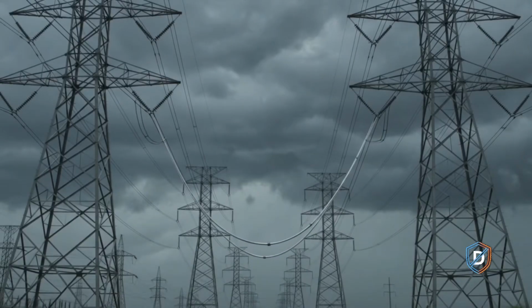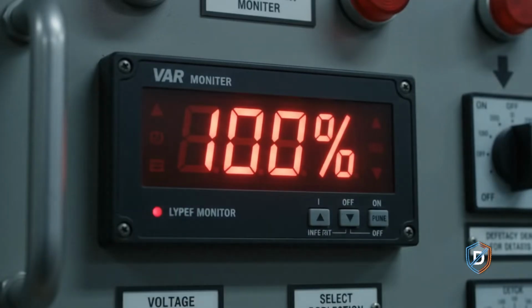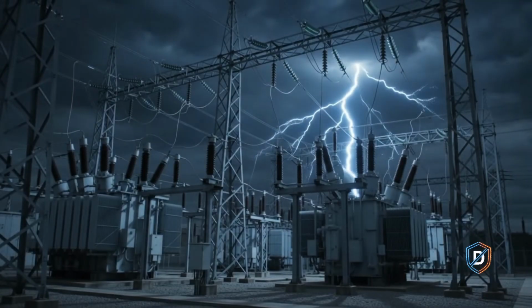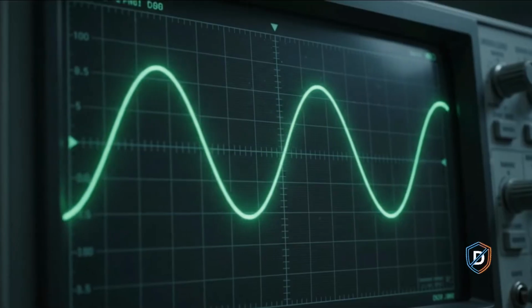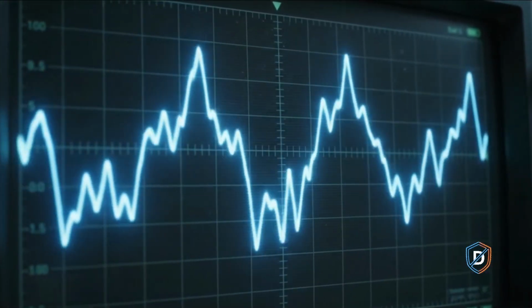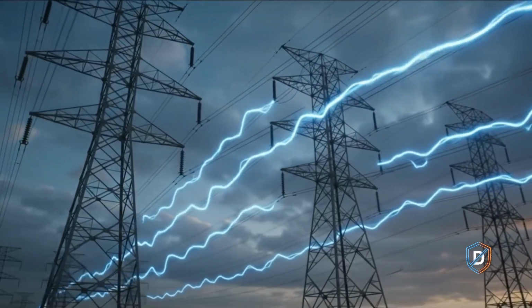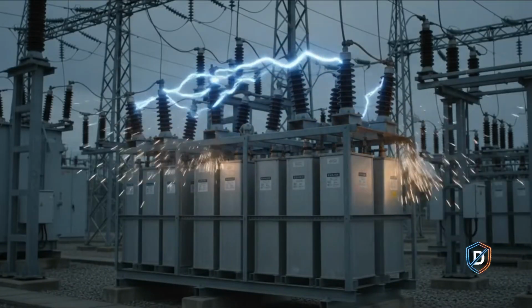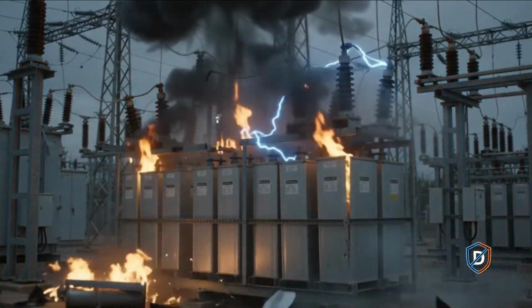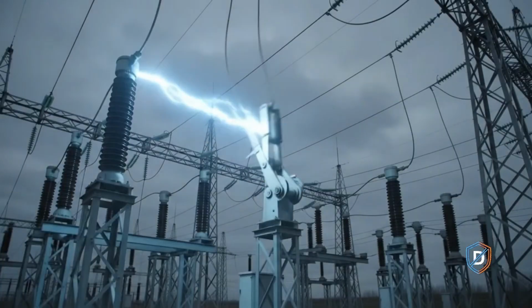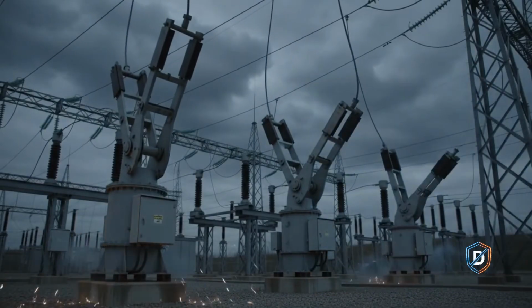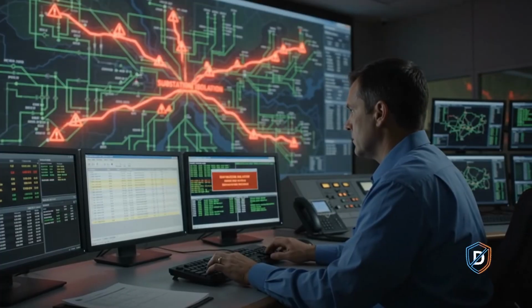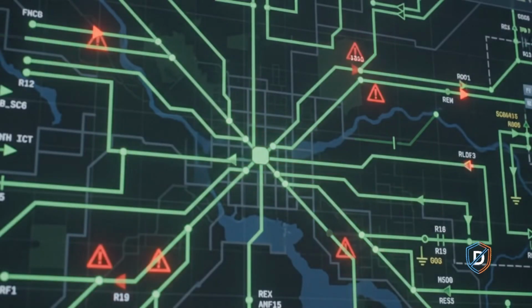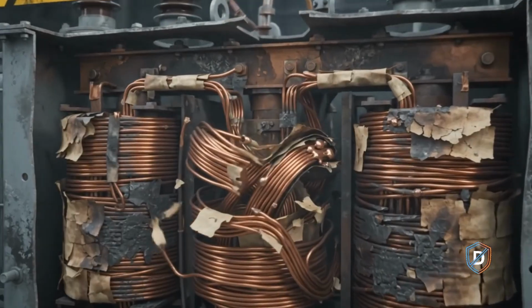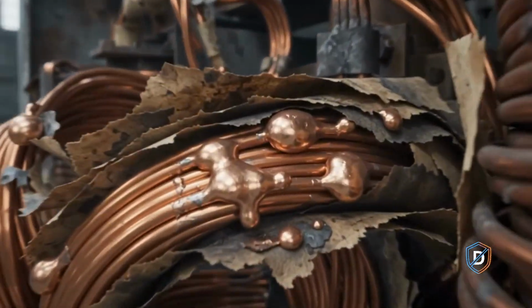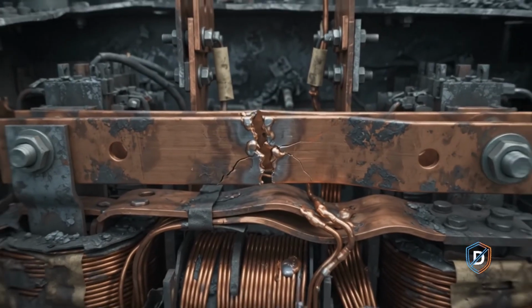Saturated transformers consume massive reactive power, causing grid voltage levels across whole regions to collapse. Distorted magnetic fields generate dangerous harmonic frequencies that pulse down transmission lines. Automated protective relays detect the distortion, instantly disconnecting multiple substations simultaneously. Even if the grid survives the initial surge, internal copper windings are permanently warped beyond repair.